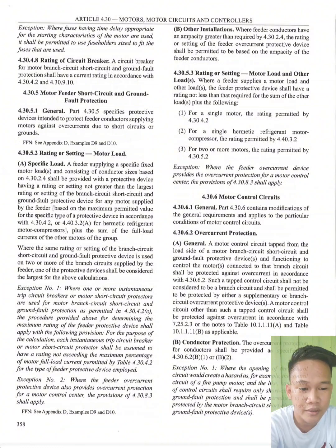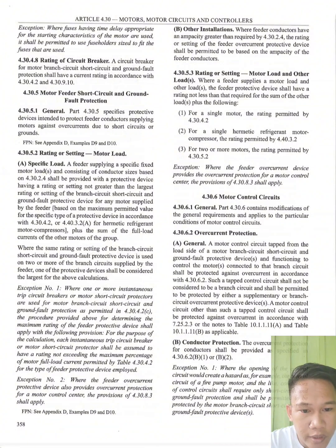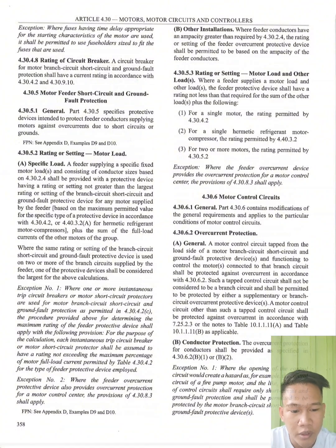4.30.6 motor control circuits. We have 4.30.6.1 general. Part 4.30.6 contains modifications of the general requirements and applies to the particular conditions of motor control circuits. Next, 4.30.6.2 overcurrent protection. General: a motor control circuit tapped from the load side of a motor branch circuit short circuit and ground fault protective device and functioning to control the motors connected to that branch circuit shall be protected against overcurrent in accordance with 4.30.6.2. Such a tap control circuit shall not be considered to be a branch circuit and shall be permitted to be protected by either a supplementary or branch circuit overcurrent protective device.